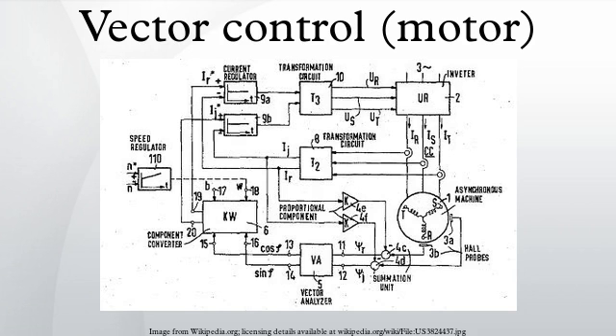The control system of the drive calculates from the flux and torque references given by the drive speed control the corresponding current component references. Typically proportional integral controllers are used to keep the measured current components at their reference values.